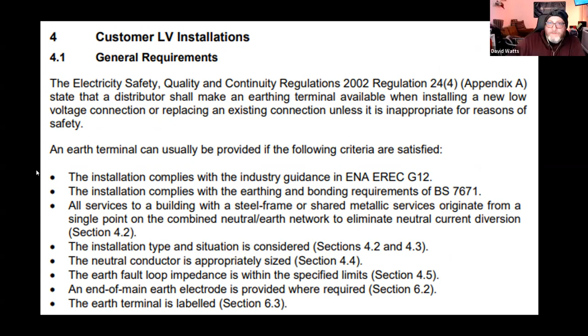This was an interesting one. Only one service and earth terminal should be provided to a customer or building. Multiple services to a building or customer are not recommended, as multiple services can cause neutral current diversion. Now, I can tell you that at a London Underground station, there are 6 DNO services.